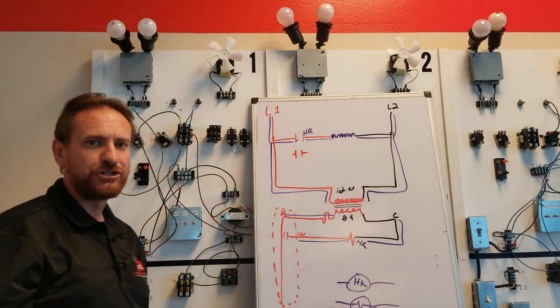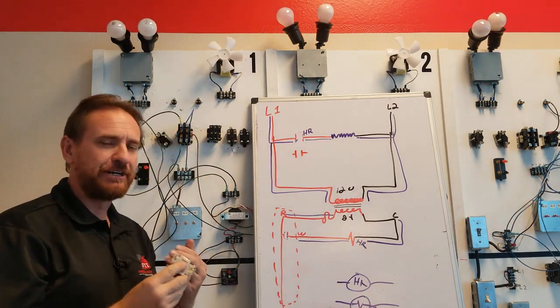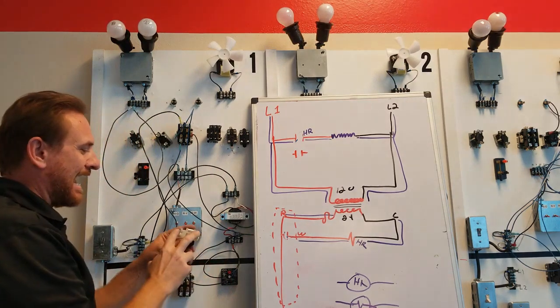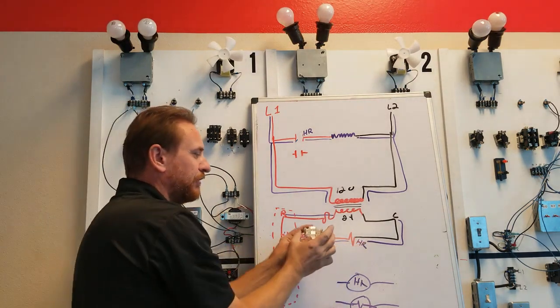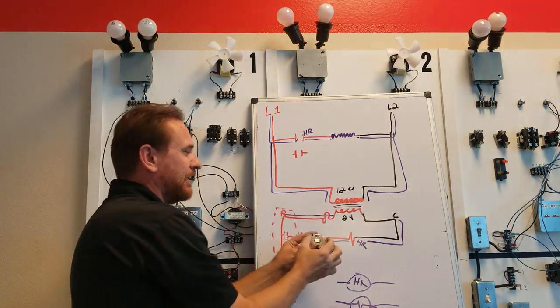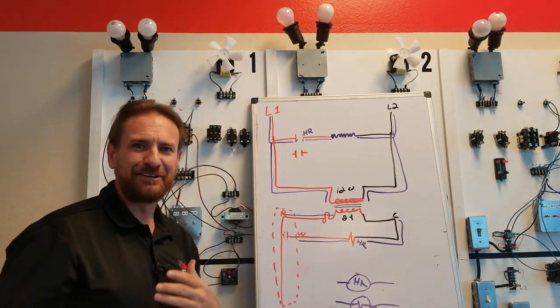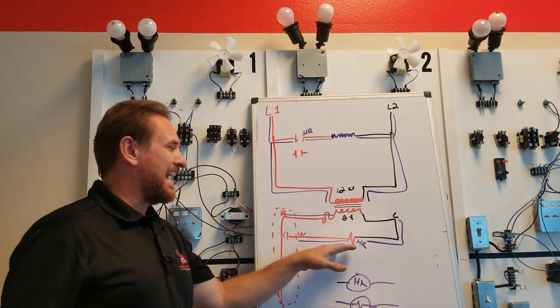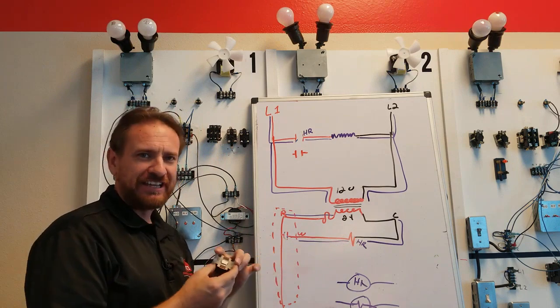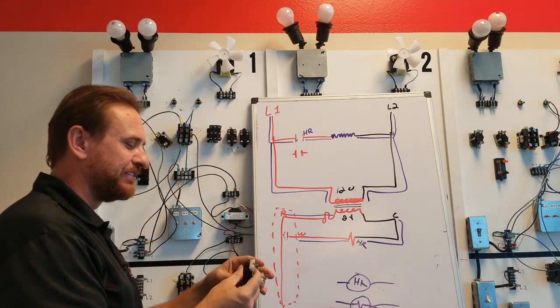For commercial, they are not, so you have to read to make sure it's the right voltage. I have to make sure only low voltage goes to this side. If I try to put high voltage here, even by accident, because people make mistakes, we're going to have a problem because this is designed for a 24 volt difference.